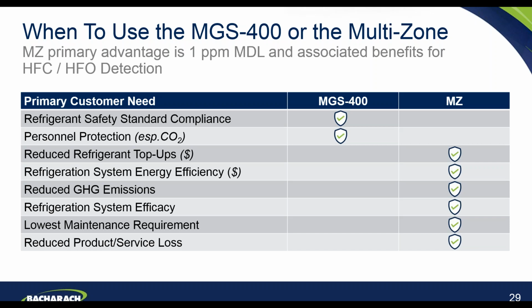And the key differential with that is the capability to measure down to just 1 part per million on the Multizone. So what that gives you is the capability to really identify at a very early stage relatively small leaks in an environment and tie that into a philosophy of refrigerant management and reduction on refrigerant losses. The MGS-400 series, as I say, is very much targeted and designed to support the compliance market for EN378, for ASHRAE 15, to provide personnel protection in the event of a relatively significant leak.